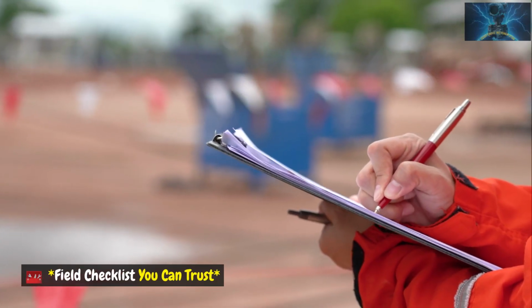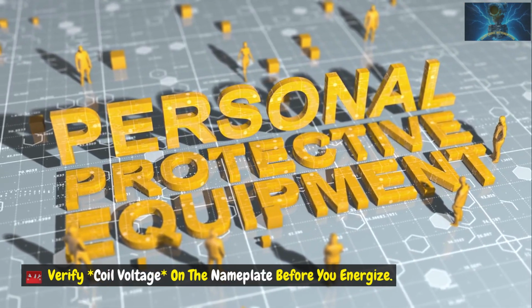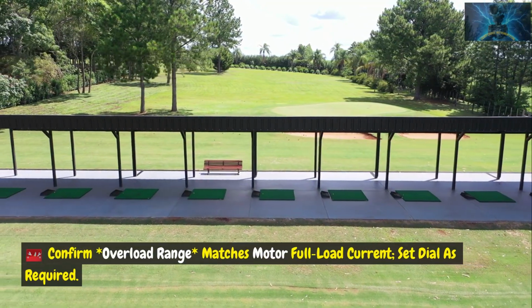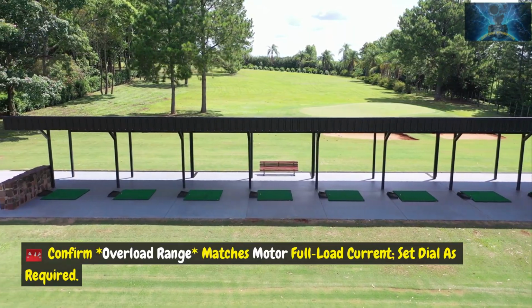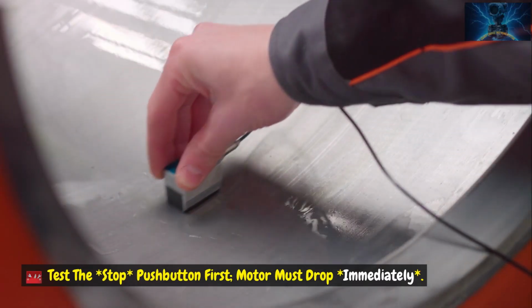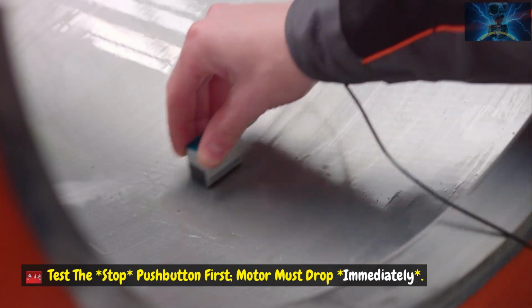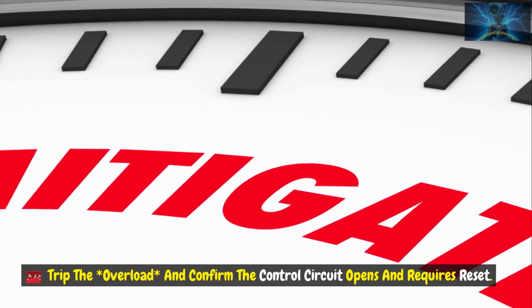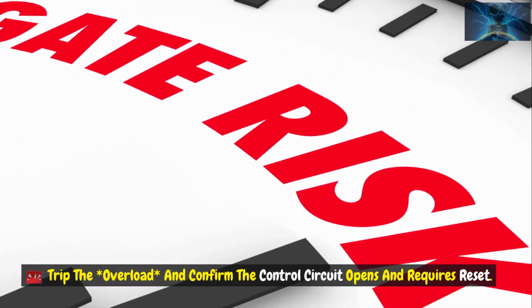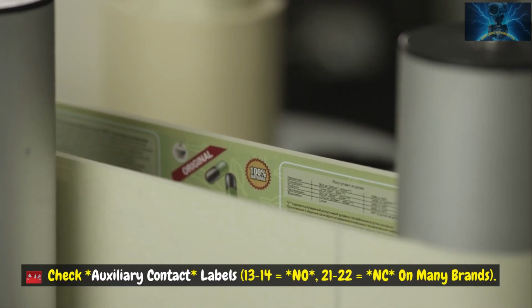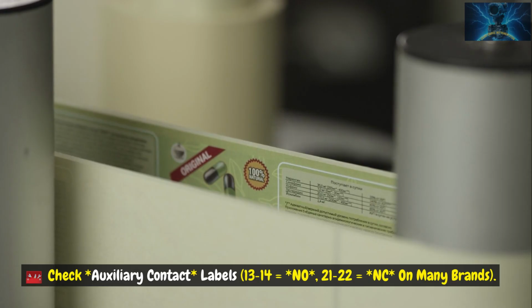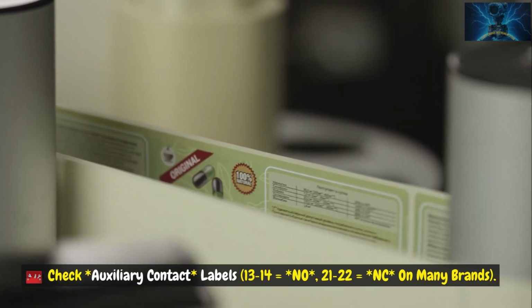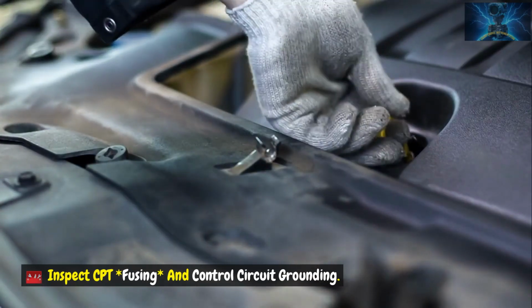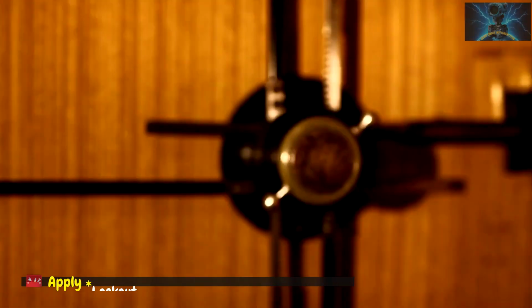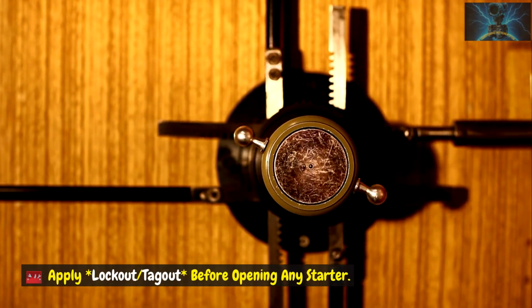Field checklist you can trust. Verify coil voltage on the nameplate before you energize. Confirm overload range matches motor full load current. Set dial as required. Test the stop push button first. Motor must drop immediately. Trip the overload and confirm the control circuit opens and requires reset. Check auxiliary contact labels: 13 to 14 is NO, 21 to 22 is NC on many brands. Inspect CPT fusing and control circuit grounding. Apply a lockout/tagout before opening any starter.